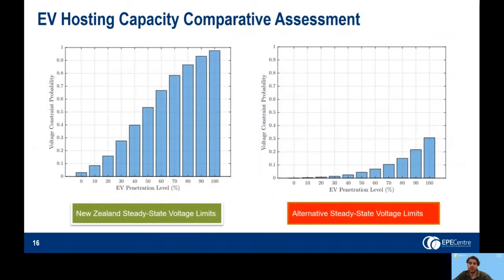What I've shown here are the voltage constraint probabilities using both the New Zealand voltage limits and the proposed alternatives. When using the New Zealand voltage limits, there is a small chance of a voltage constraint even at the 0% penetration level. Furthermore, the voltage constraint probability increases significantly as the EV penetration level increases. So that's the New Zealand voltage limits as seen there on the left.